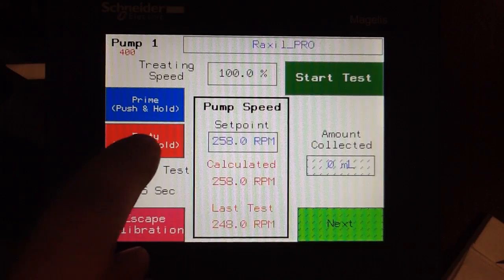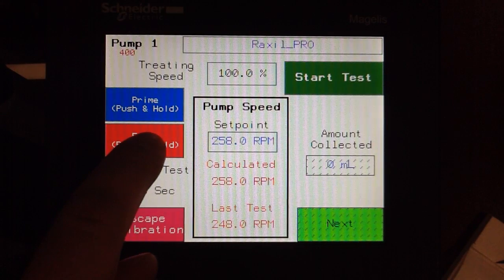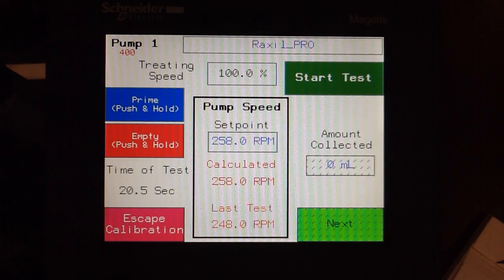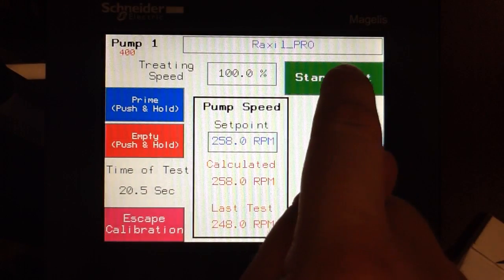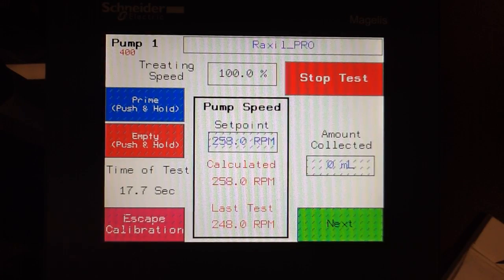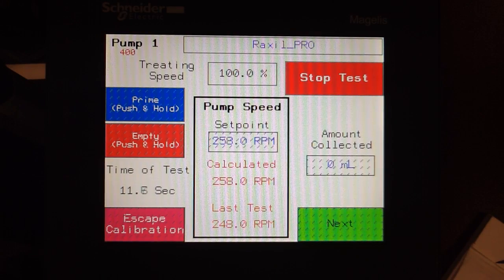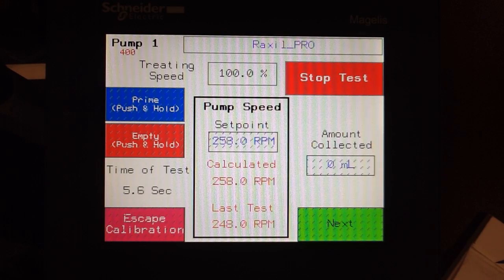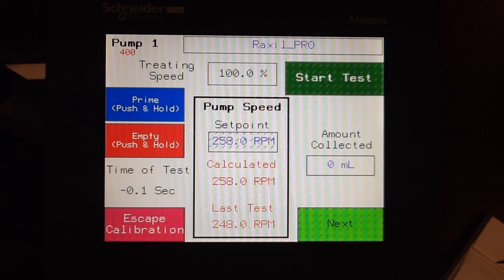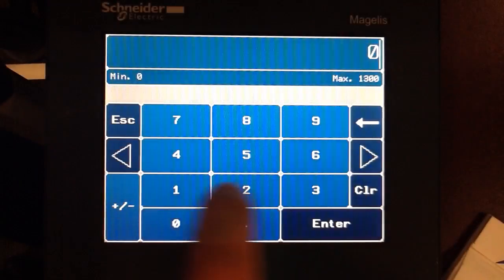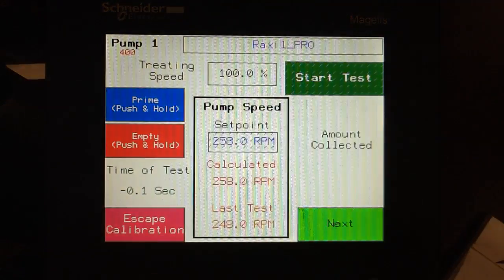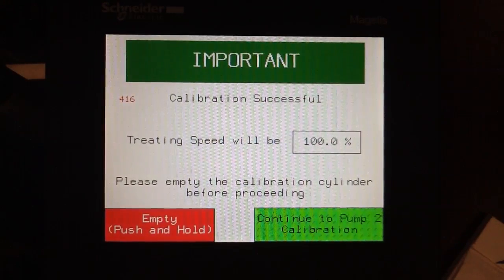We then simply empty the cylinder to the zero mark. We now have a new calculated set point, and we touch Start Test. We now enter the amount collected in the cylinder — it's now 1000 mils. Select Next, and we now have a successful calibration.